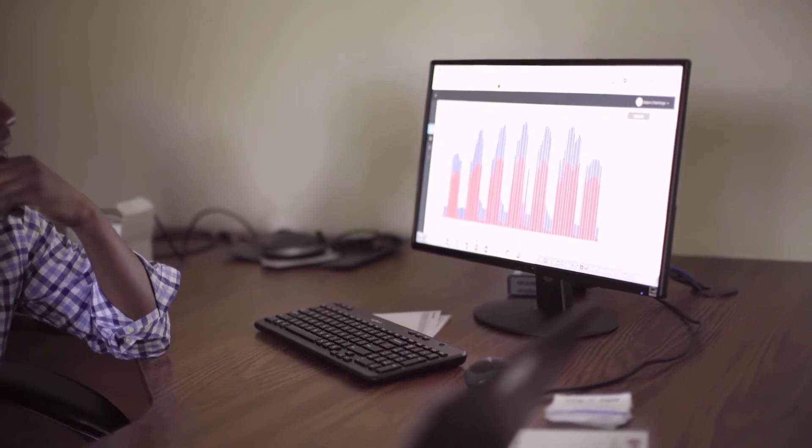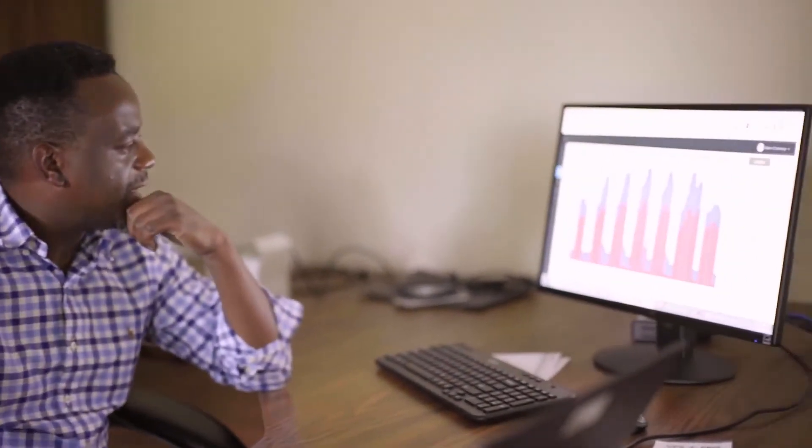There's no difference between a weekend and a weekday profile. Wow, look at the base load — 100 kilowatt hours. That's a lot. They might be unnecessarily running the HVAC system when they could easily switch it off and get some savings from there. It looks like projections are very similar, if not exceeding what we had said. We're looking at a 15 to 20 percent savings. And if we could capture 15 to 17 percent in energy savings from the overall energy consumed by that facility, we know that we have a home run.